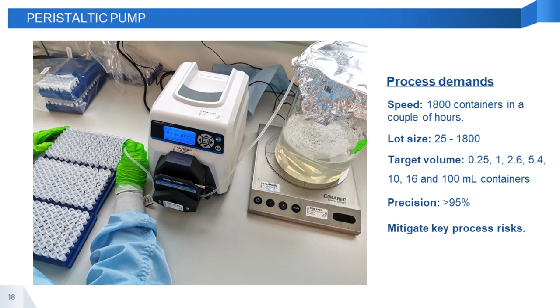Okay, let's go with the speed and precision of this peristaltic pump. In our pump system, the speed can be adjusted depending on the needs, from 0.25 to 3,400 milliliters per minute. The target volume in which we needed the most significant speed change was the 100 milliliter bottles. With the dispensers, it took 10 seconds for each of them. With the peristaltic pump, it just takes around 4 seconds for each bottle.